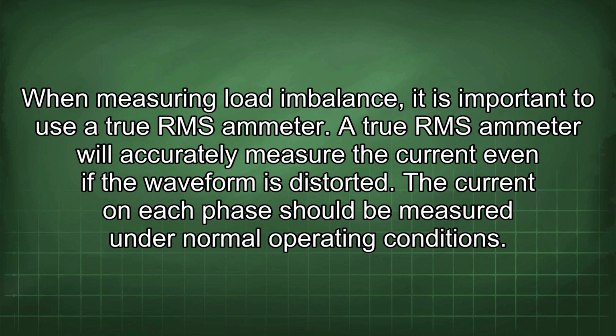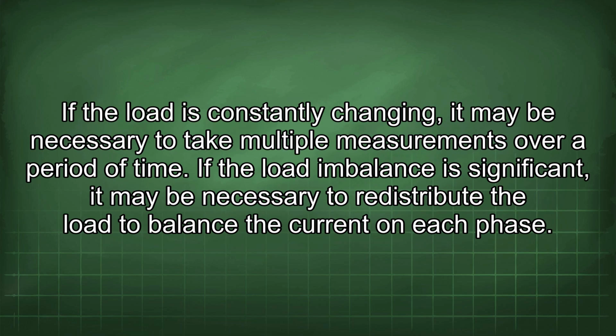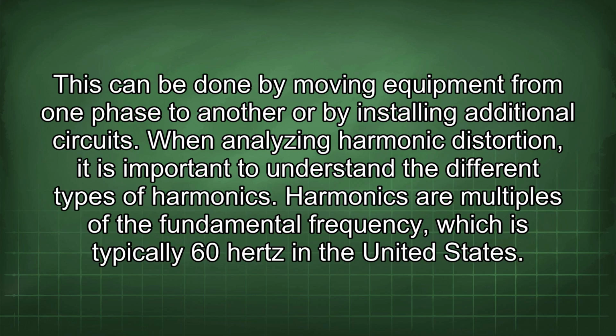The current on each phase should be measured under normal operating conditions. If the load is constantly changing, it may be necessary to take multiple measurements over a period of time. If the load imbalance is significant, it may be necessary to redistribute the load to balance the current on each phase. This can be done by moving equipment from one phase to another or by installing additional circuits.